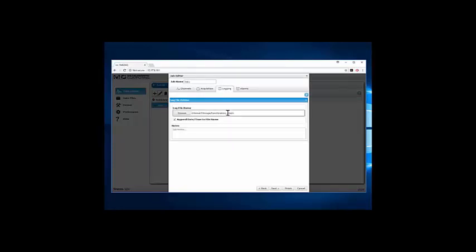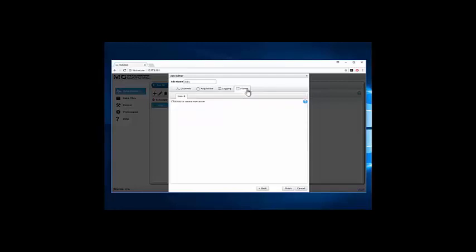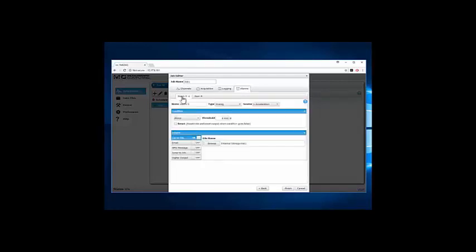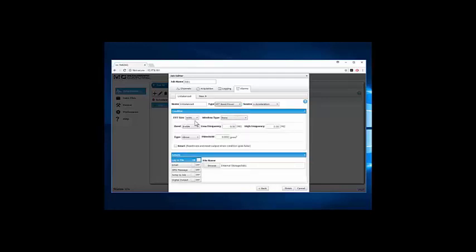Next, I'll go to the Alarm tab and add a new alarm. I'll name it unbalanced and choose the type. You can create an alarm based on an analog or digital channel, or you can also alarm based on FFT band power for this particular device. You can set up the FFT size you want to check for your alarm condition, any window function, based on in-band or out-of-band frequencies, and set the power threshold for your alarm condition.